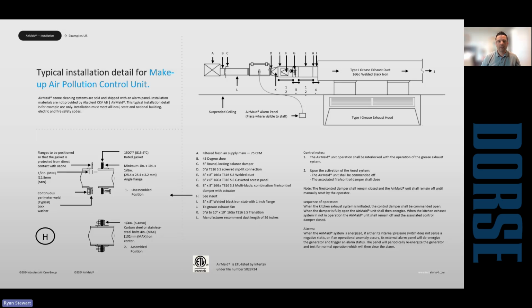to get it into the ductwork. Some of the components that go along with it, you're going to have a fire damper. So if there's a fire in the grease duct, it can't spread into this unit off the side. And then you'll have a balance damper so you can control the volume of air across those UV bulbs. So you have the right concentration of ozone to be effective at reacting with the grease.